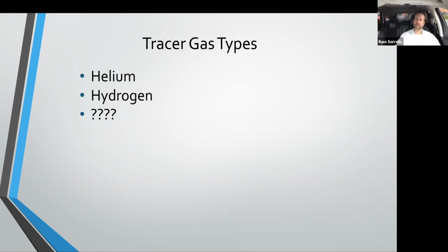Okay, excellent. Now, what other? So we've talked about helium, we talked about hydrogen. I mean, there are a number of other tracer gas technologies that you've enlightened me about, but I wasn't aware of until you did. People, especially in the air conditioning refrigeration industry, will actually do a leak test and use refrigerant as a tracer gas. So they'll put a little bit of refrigerant charge in the unit, and then they might put some nitrogen or air on top of it to increase the pressure.